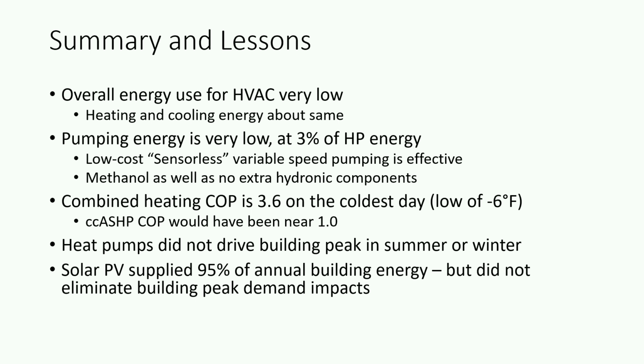And of course, a cold climate air source heat pump probably would have been pretty close to 1 at that point, to state the obvious. And the other interesting thing is, in this building, the heat pumps are not what's driving the peak demand of the building, like everyone expects, right? The expectation is building demand is driven by the HVAC system. That was not true here. The solar system was big and worked well, and it provided 95% of the energy across the year, but it didn't make the building demand any different, right? The building still peaked outside. The building peak was always outside of when the array was providing energy.